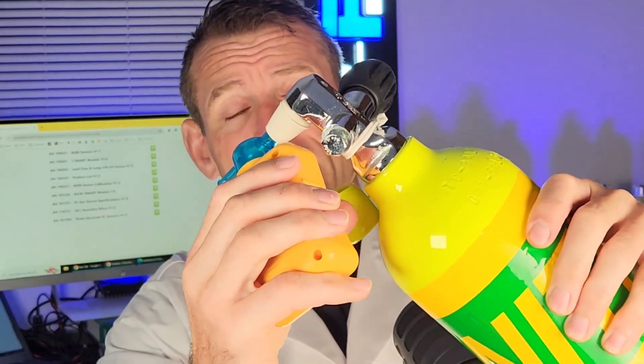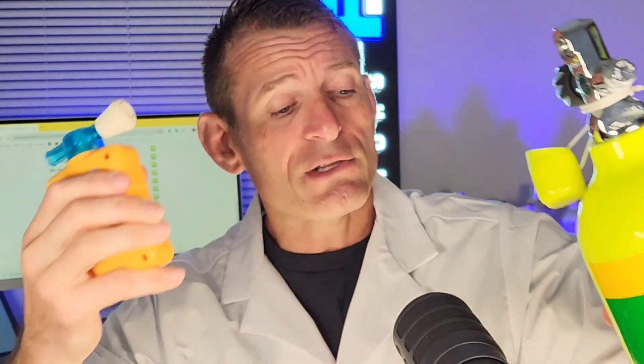The primary application for this unit was for Dr. Kaz to provide an affordable scuba oxygen analyzer on the market. All you do is pop on the dome on one side of the analyzer, just like that, and then you could test your oxygen gas cylinders for diving. It fits snugly with the rubberized dome and you could take a measurement.